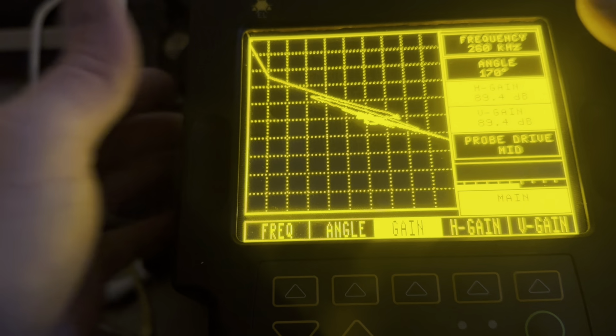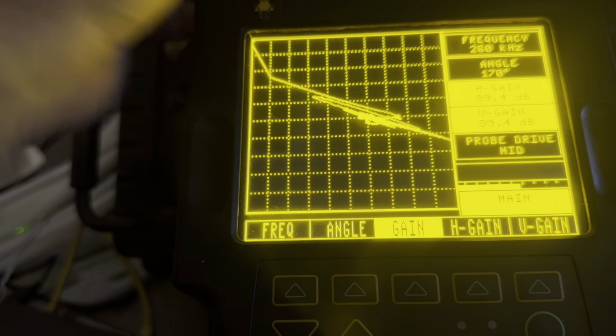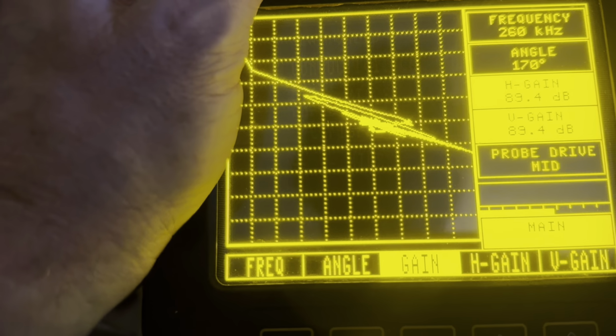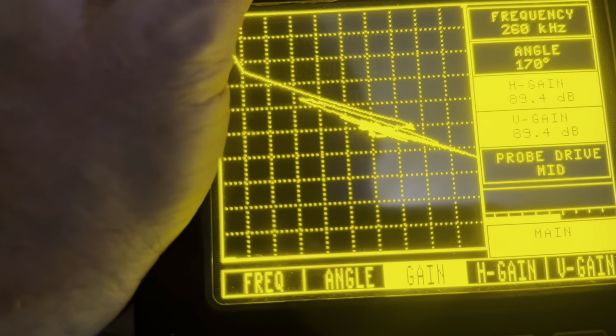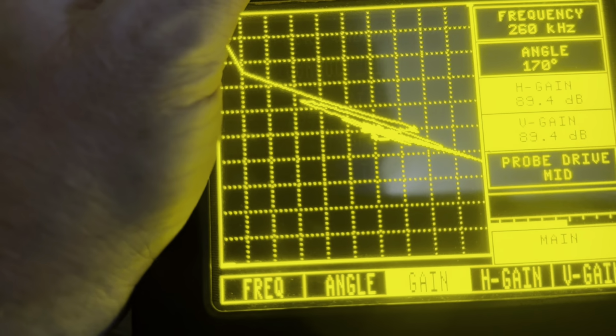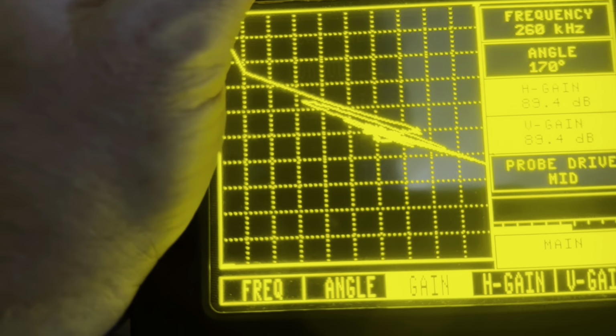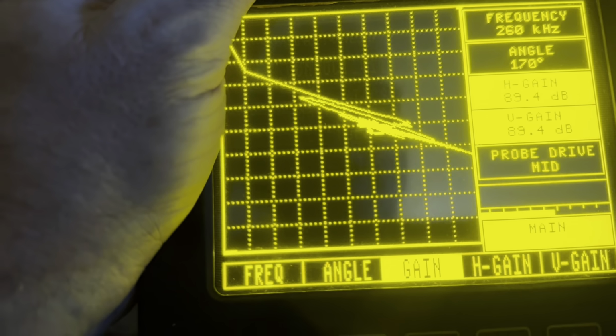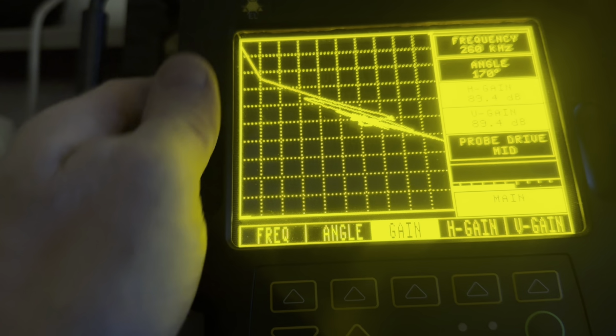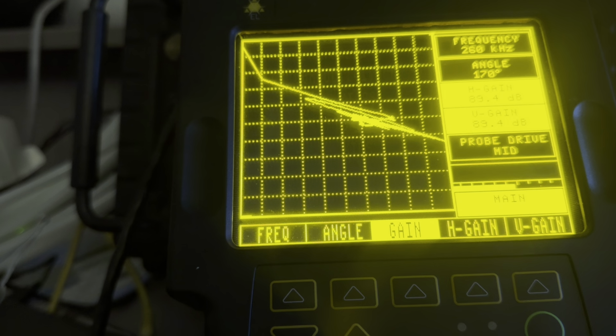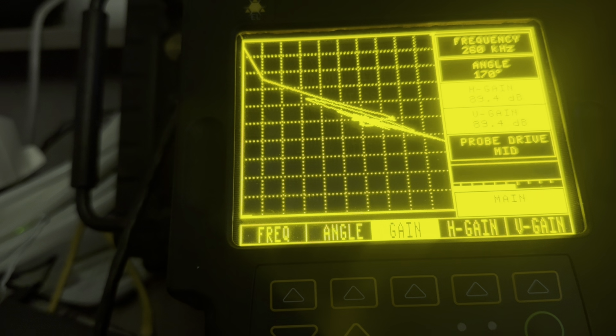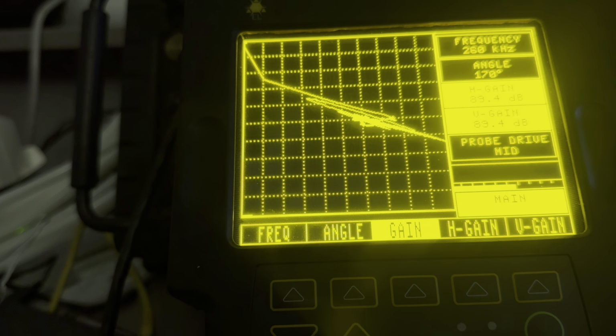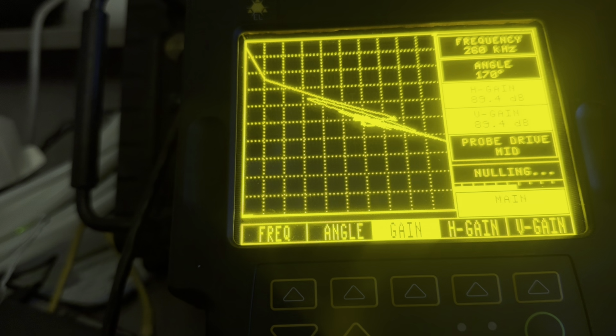So I would say most of the time, if you take a cable and it's the right cable and you hook up a probe and you're not getting a signal, chances are the probe could be dead. Your instrument could be shot, maybe you left it out in the rain, or you probably just have a setting incorrect. This is where an experienced level 2, rather than throw the probe or the tester away, will just keep playing around with the settings until he gets it right.